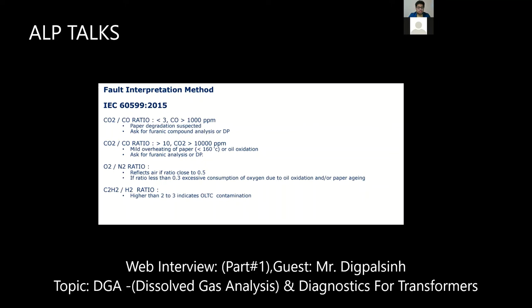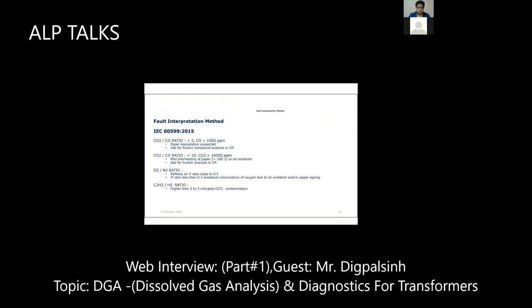But later on you go with the C2H2 and H2 ratio. If you find this value is higher than 2 to 3, then you can say your transformer tank oil may be contaminated with OLTC oil, not sure, but it is a possibility. So if you found arcing, if you found C2H2 is higher, then after that you have to go for the C2H2 and H2 ratio, so you can check or confirm whether there is OLTC contamination or not. That's it for IEC.